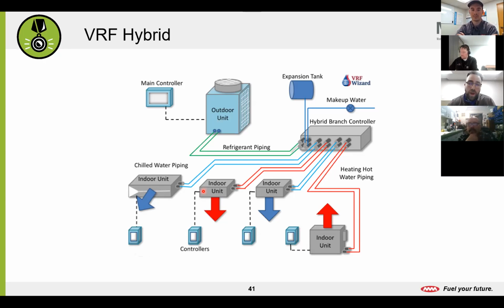As far as what that means for us on our end, well, I can tell you from the service side, if we're only dealing with a refrigerant circuit going from an outdoor unit to a branch controller, that's a lot easier to maintain, troubleshoot, less capacity for refrigerant, only dealing with water. I don't want to say that's a safer medium, but that's obviously an easier, more environmentally friendly medium to maintain and handle, especially if we do have any issues versus having to deal with refrigerant lines going throughout the building. So really neat stuff. I haven't seen it implemented yet personally, but I would be excited to see what that looks like inside of a building. Definitely a step up from the traditional VRF.